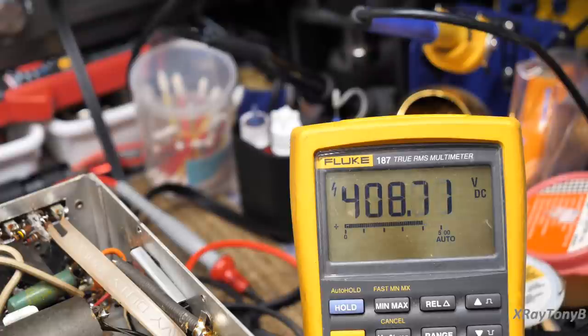So for right now, I'm going to turn this back down to 110, and it's happy. So the good news is everything looks good. I don't think there's a bad capacitor immediately, but these caps, after they've been off for a long time, I've seen where they've run for an hour or so with no problems, and all of a sudden just boom, they short out. So we are going to eventually replace them.